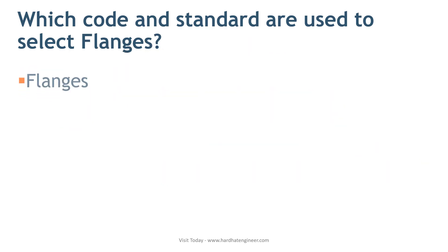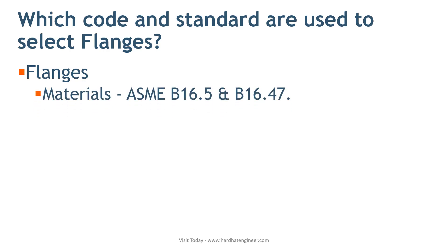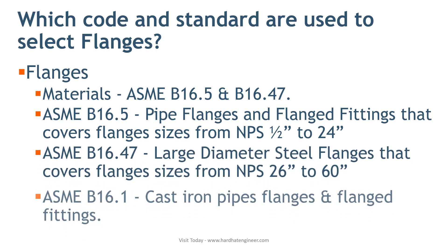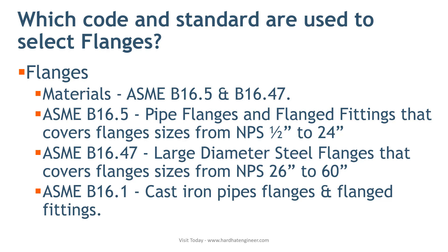Next is flanges. The list of materials used to manufacture flanges is covered in ASME B16.5 and B16.47. ASME B16.5 is the standard for pipe flanges and flanged fittings covering sizes from NPS 1/2 inch to 24 inch, whereas ASME B16.47 is the standard for large diameter steel flanges covering sizes from NPS 26 inch to 60 inch. ASME B16.1 is the standard for cast iron pipe flanges and flanged fittings.